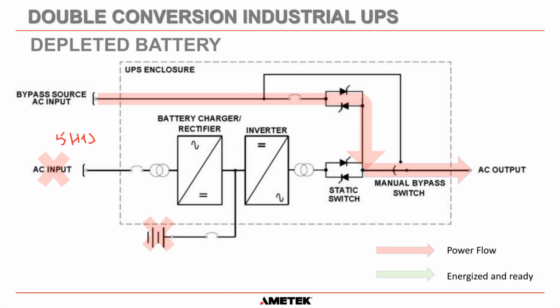And for a lead acid battery, all the battery manufacturers say that you should not discharge a lead acid battery below 1.6 volts per cell. You could do irreversible damage to a lead acid battery if you go past 1.6 volts per cell. And in truth, the industry standard when people size a UPS is that the low voltage cutoff is actually 1.75 volts per cell to give you a little bit of a buffer.